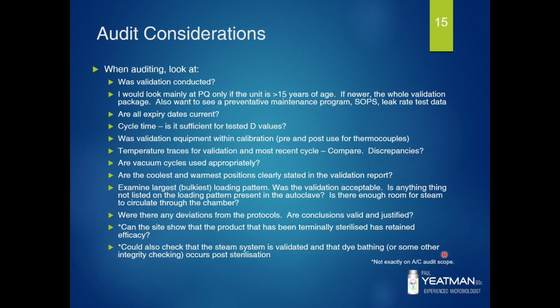You want to examine the coolest and warmest positions, which will be stated in a validation report. You want to make sure that they've been identified, and if they have been identified, then were they investigated? So do you have data that shows that these cold spots, not so much the warmer spots, but most of the cold spots, is it possible to sterilise equipment in these positions? If yes, brilliant. You want to examine the largest or bulkiest loading pattern. Was the validation acceptable, and is there anything not listed on the loading pattern present in the autoclave?